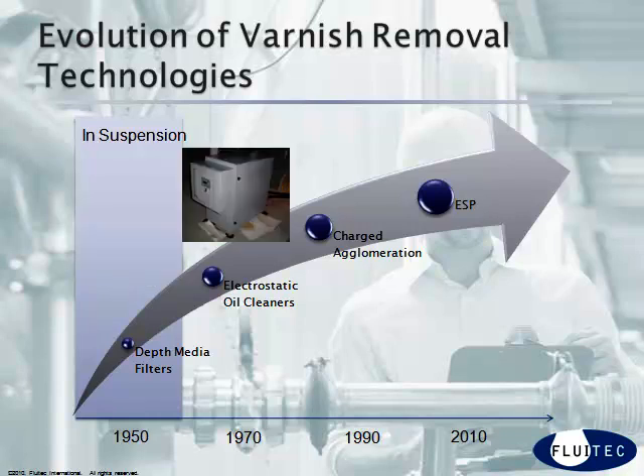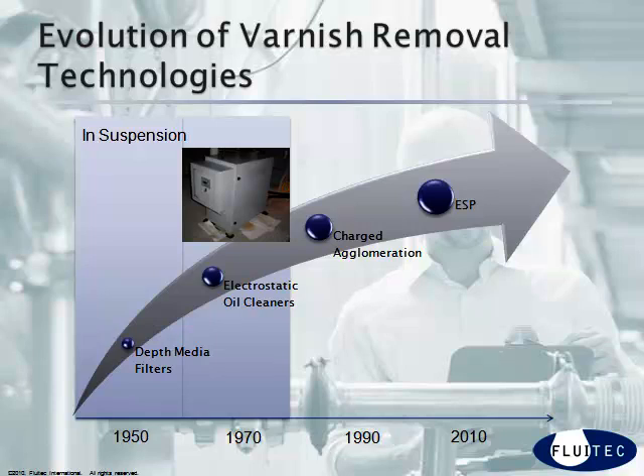Electrostatic oil cleaners were developed in the 1970s. They work by applying a charge to the submicron contaminants as they flow through a collector. They are designed to work with non-conductive fluid, so a little bit of water contamination will impact its performance. Depending upon the manufacturer, they can be effective. However, they are only designed to remove contaminants in suspension.